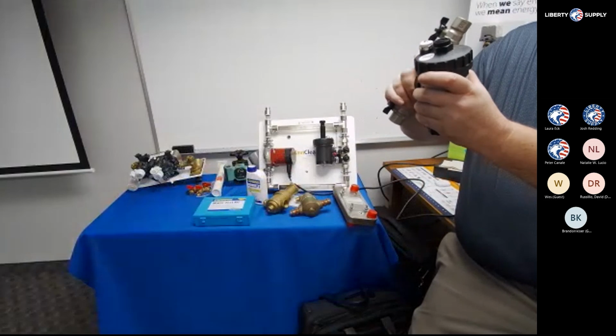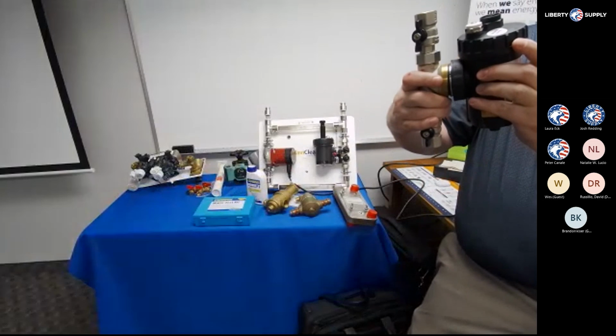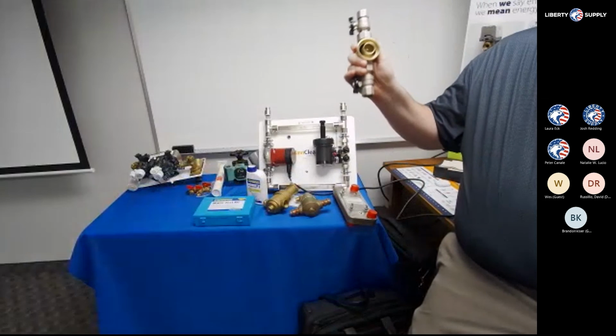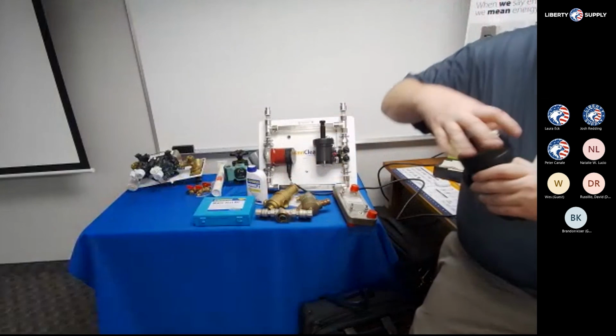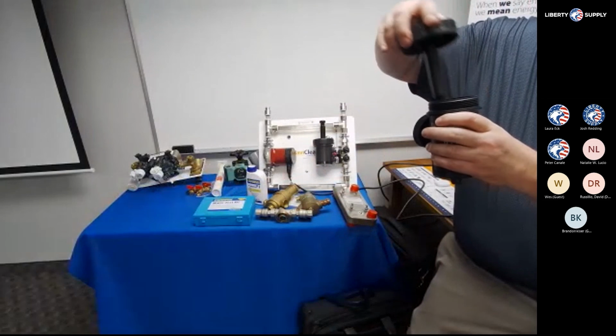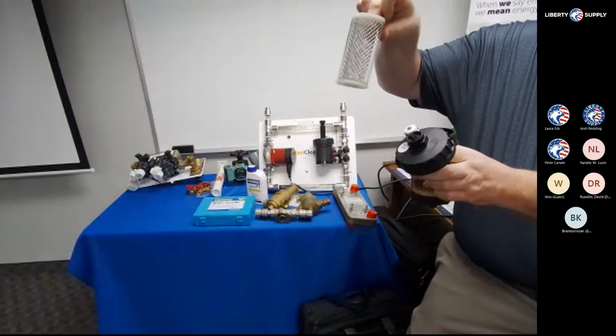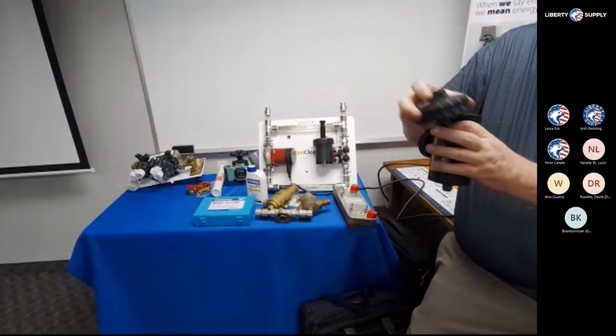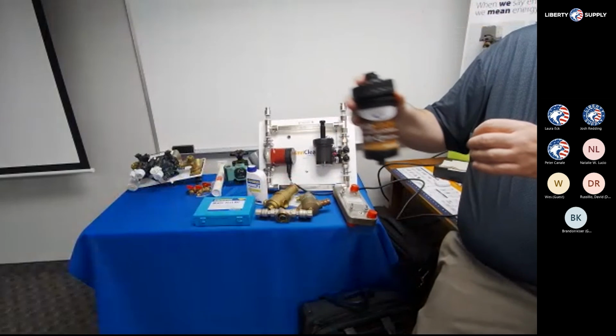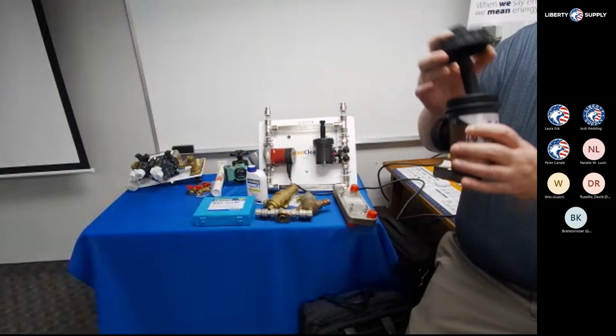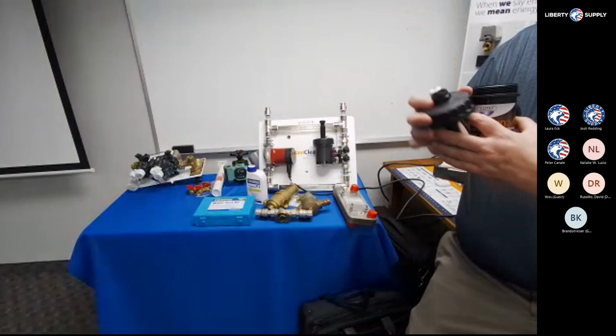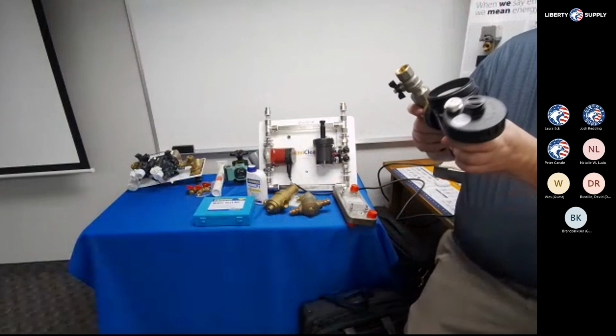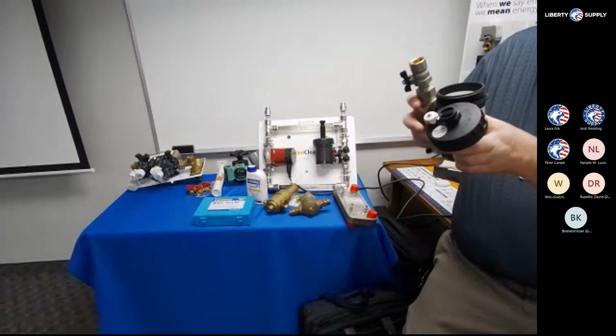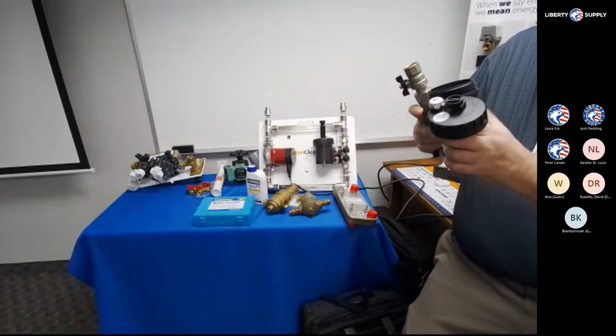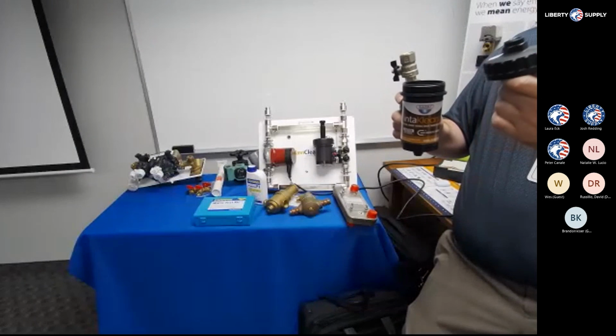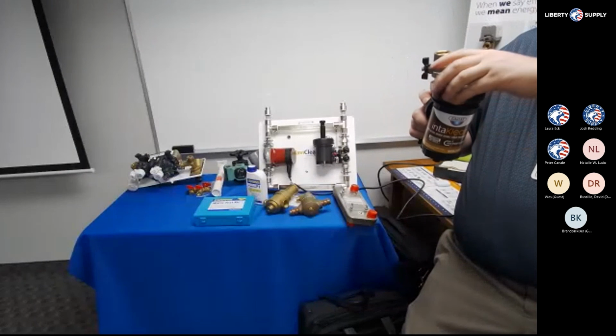Also, to clean these smaller ones, all we do is undo the little union nut on the back side. I pull this off of the system and I can now open up this canister. Again, we're talking about one that has a filter screen in it, so it will deal with sediment. I can pull this whole assembly, go over to a slop sink, wash the whole assembly out, reassemble that system back onto the piping, and fill this back up with my inhibitors and seal everything back up.